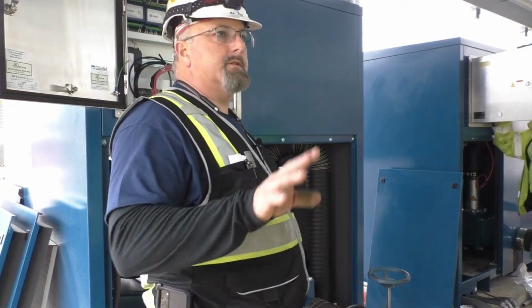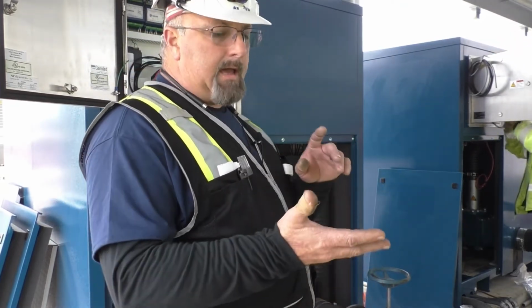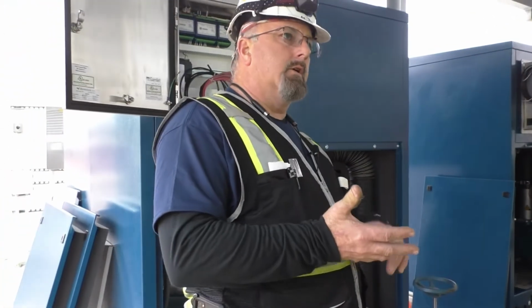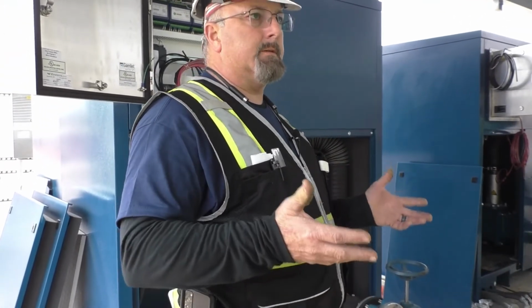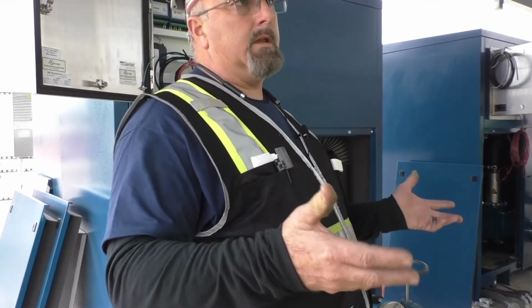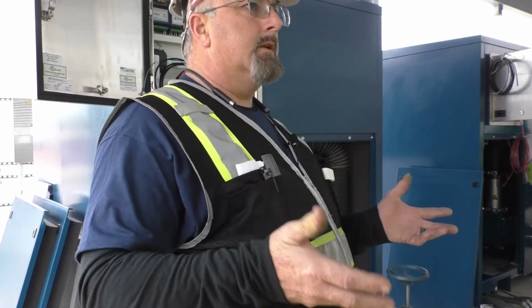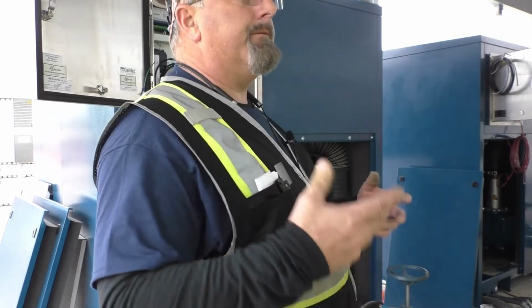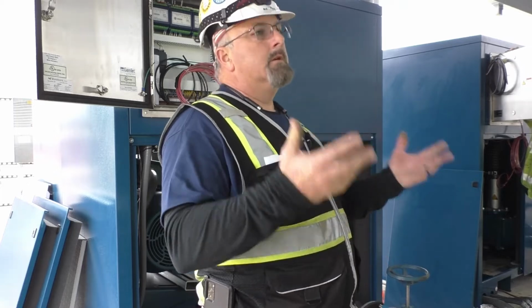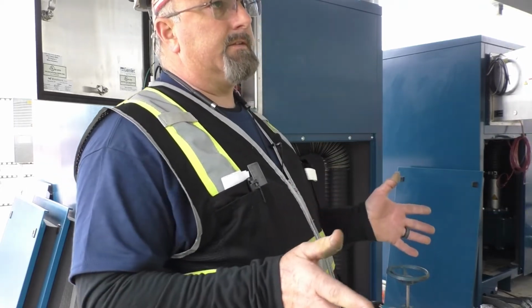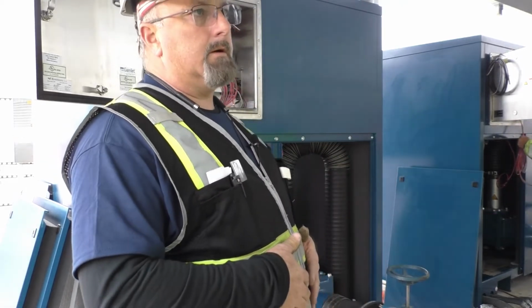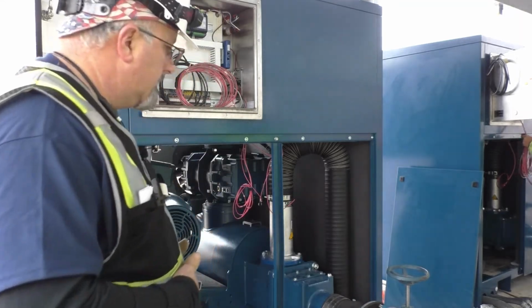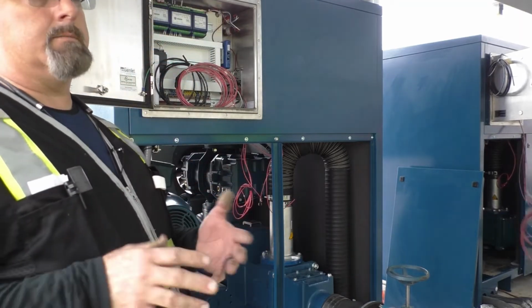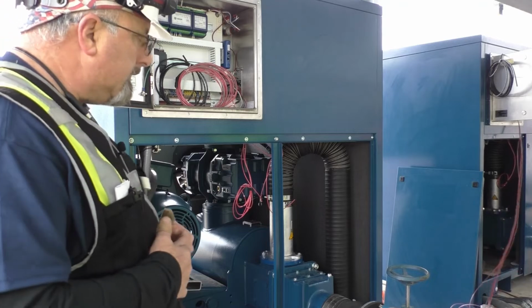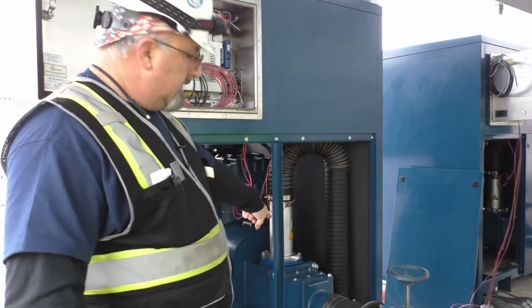Only if you're doing something electrically as I described, i.e. you had a motor fail, you had a drive fail or something like that, or something changed on your incoming power, you would want to take your belts off, verify your motor rotation, and then, as long as everything was okay, you could put the belts back on. That's the only time that comes into play. If it's just backflow that's doing it, that's where you want to go.